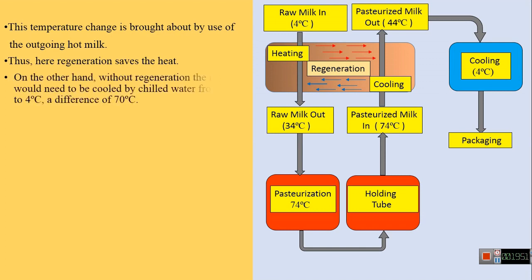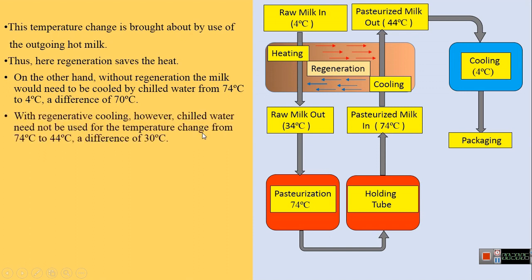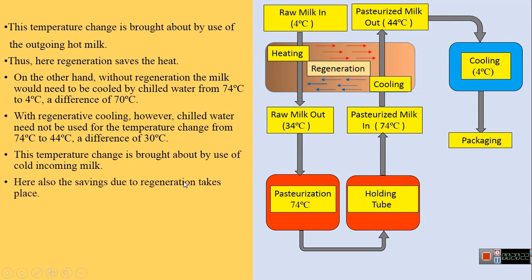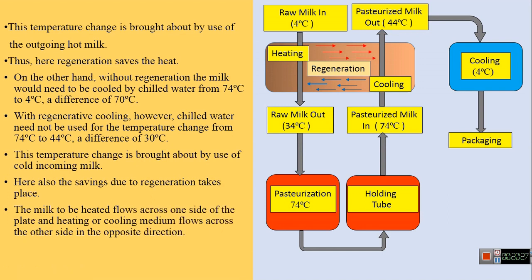On the other hand, without a regeneration system, we would have to cool the hot pasteurized milk from 74°C to 4°C using chilled water — a temperature difference of 70°C. However, in the regeneration section, chilled water is not required for reducing the temperature from 74°C to 44°C, as this is achieved by the incoming cold milk. Thus, in the regeneration system, the exchange of heat between incoming cold milk and outgoing hot milk saves energy and reduces the cost of the process.